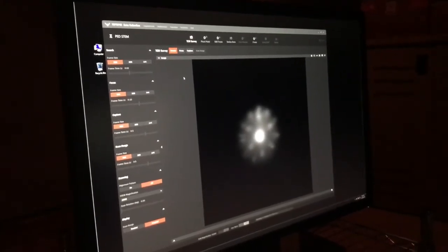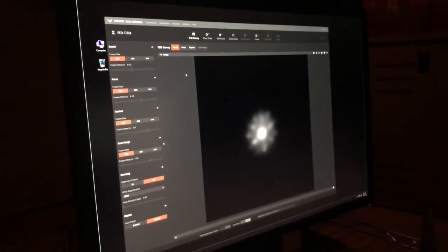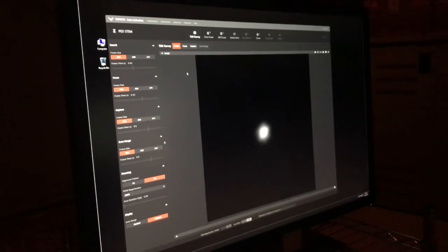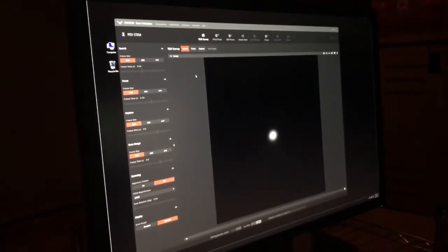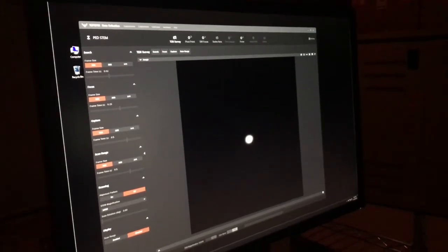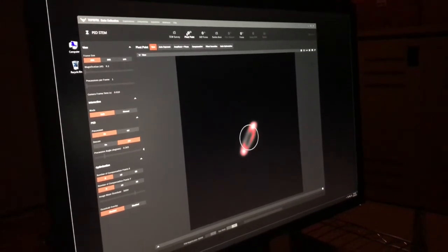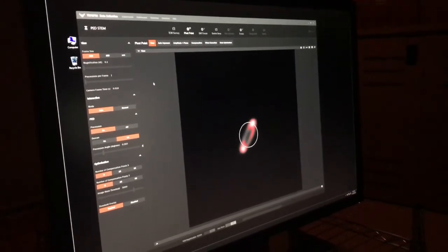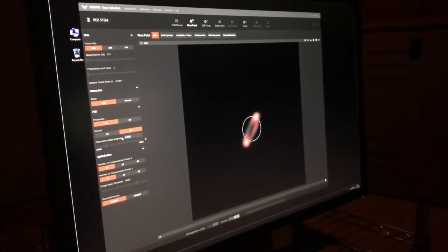And you can see the specimen is not at the exact eccentric height, so use Z to bring the specimen to the right eccentric height. Then move back to the vacuum. Moving forward, click on the pivot point. In this step, make sure we define the precession angle. In this example, we'll use 0.3 degrees.